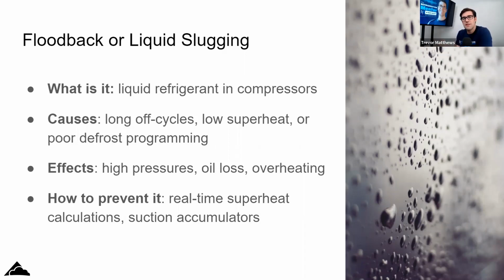So there are so many different things that you can check, because if your oil reservoir is full, but it's still washing out the oil, by analytics, you can tell, okay, my oil reservoir is good, I should be feeding, but now my compressor doesn't have any oil in it. The differential is too low. That's probably floodback happening. So there's lots of different analytics you can do. Measuring the oil temp, measuring the discharge temp for floodback.